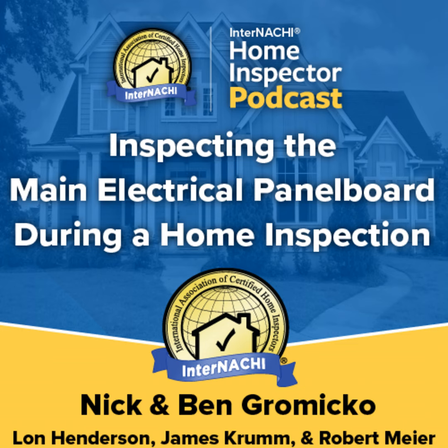Sub-panel or additional distribution panel board. A new panel board should not exceed 80% of its full capacity, which means that it should have open slots for future additional circuits. However, an older panel board may not have room for additional circuits, and a sub-panel may be added. Sub-panels or additional distribution panel boards are typically powered by a double pole breaker in the main service panel board with a 4-wire SER feeder cable that carries 2 hots, 1 ground, and 1 neutral conductor.